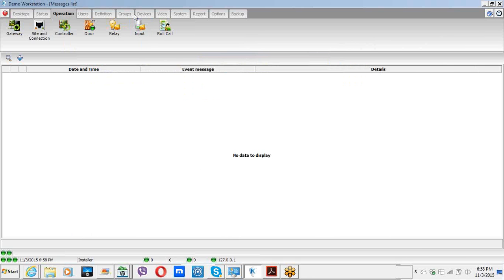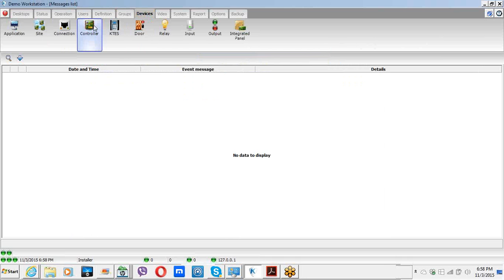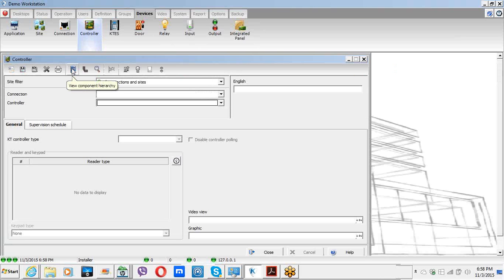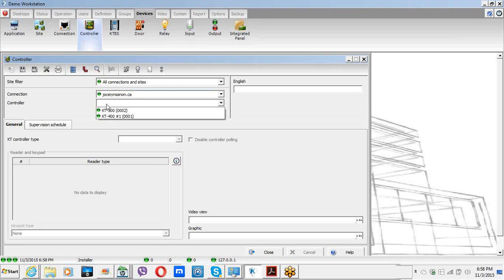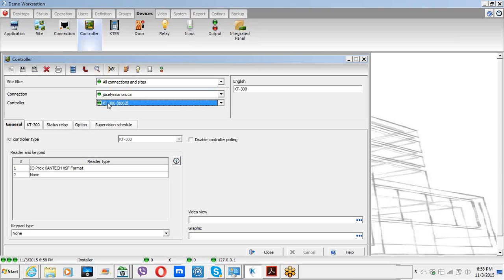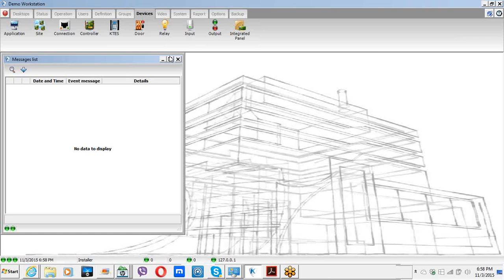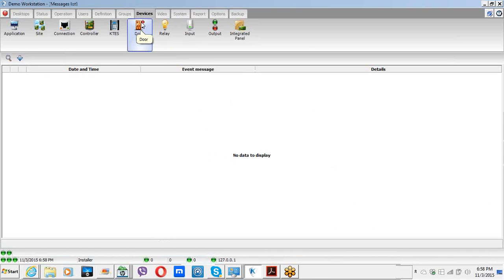First, we need to remember: in Corporate and Special edition, the anti-passback is at the controller level. Meaning, in my system right now I have two controllers, so I will automatically have two different arrays of anti-passback. To set up the anti-passback, we need to first activate it at the controller level — otherwise it will not be available at the door.